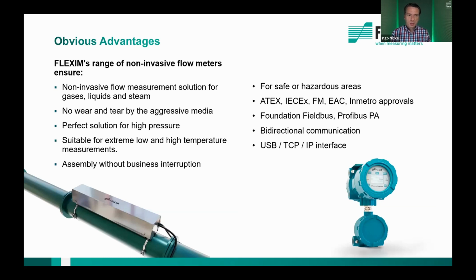At the end, I want to sum up the advantages. As the transducers are clamped on to the outside of the pipe, the measurement system is not exposed to any wear, tear, or abrasion from the medium flowing inside the pipe, and is thus very reliable and durable. Installation requirements are non-existent. No cutting or welding has to be done to the pipe. Costly process shutdowns are completely avoided with a clamp-on solution. Moreover, the measurement system does not cause any pressure loss, which in the end avoids unnecessary energy cost for the customer.